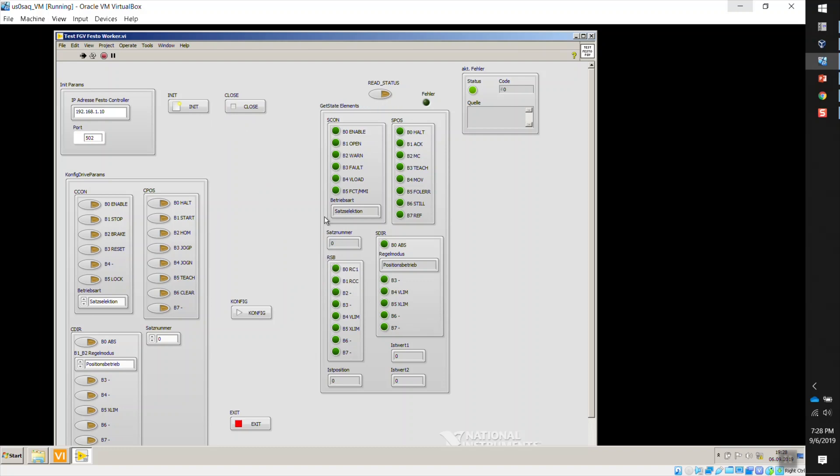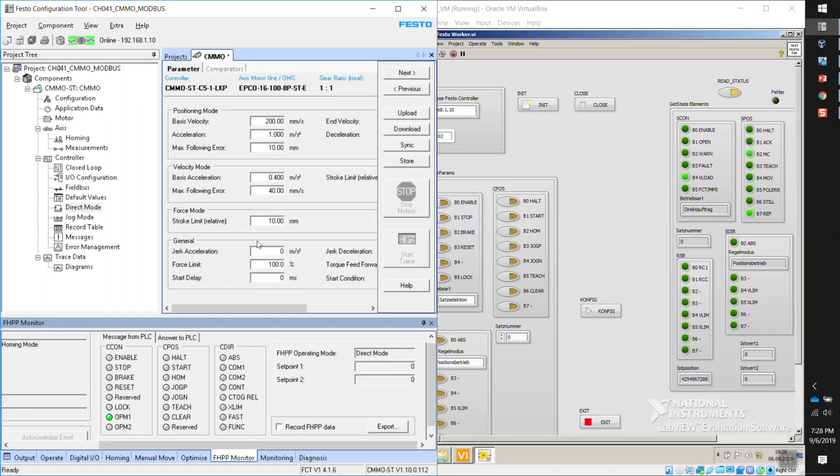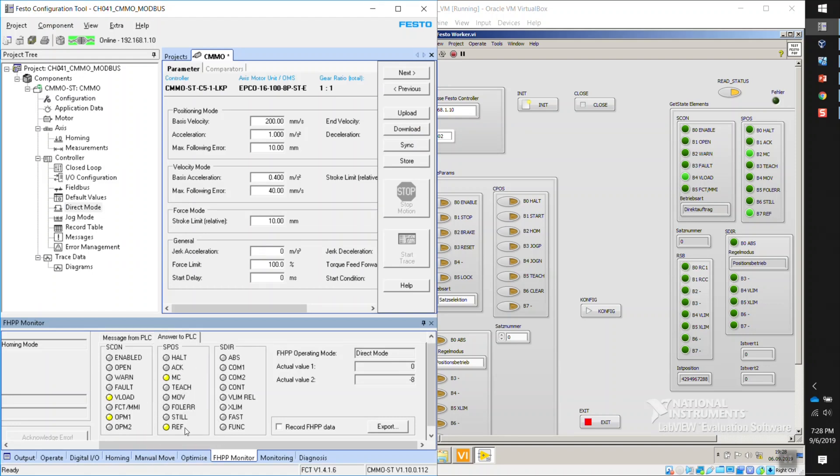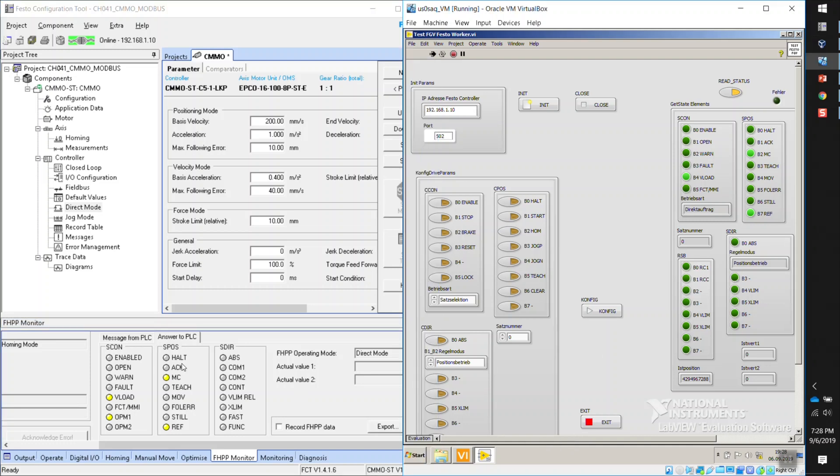Now, I'm not getting anything here because I need to activate this button to start getting some feedback. Now I'm going to put this side by side so we can see what's going on here in FCT as well. Answer to PLC. So here, FCT saying that the CMMO is sending a motion complete, a reference bit, voltage load, and OPM1, right? And it's exactly what we have here.